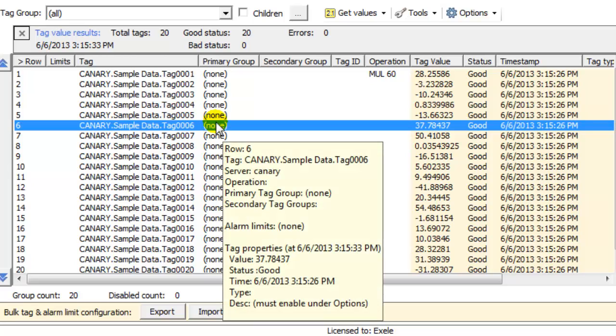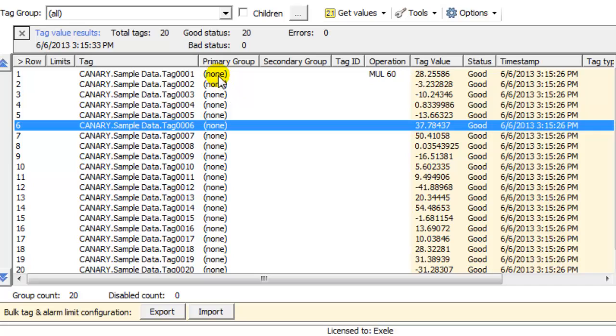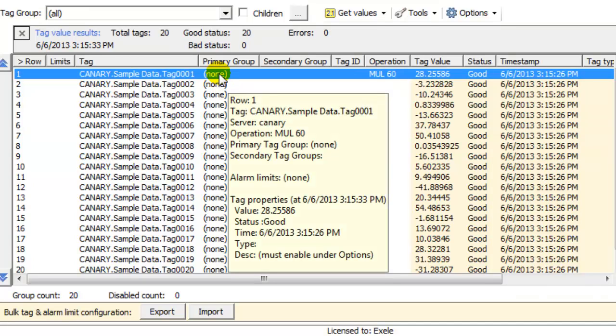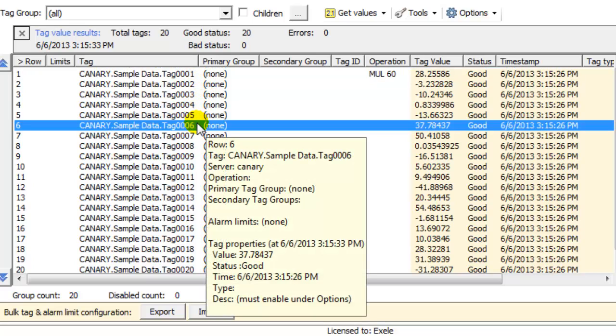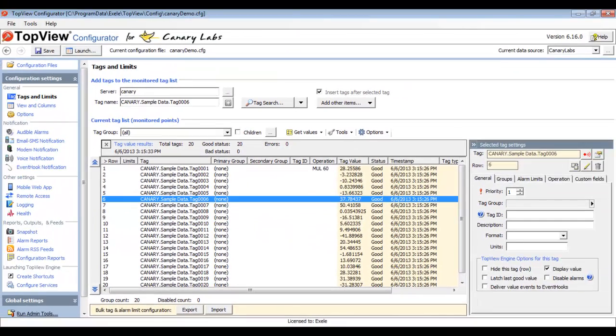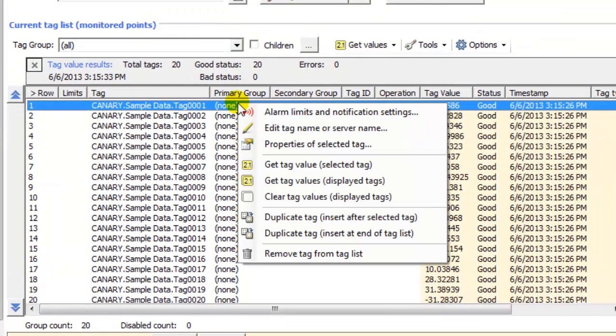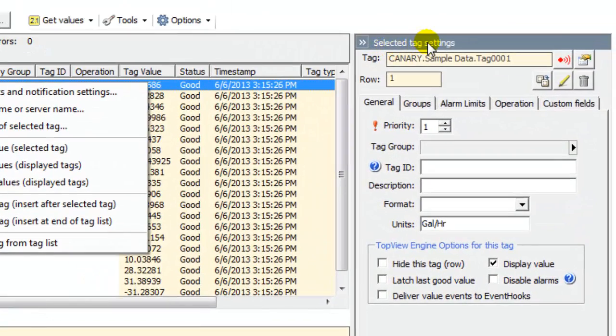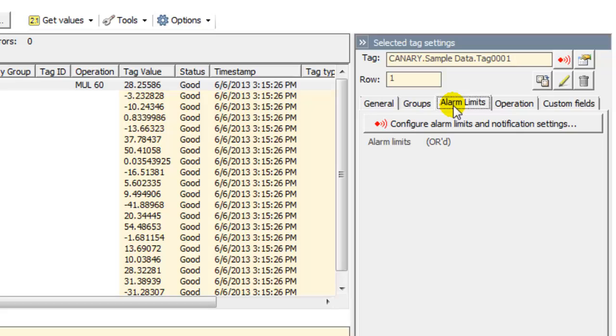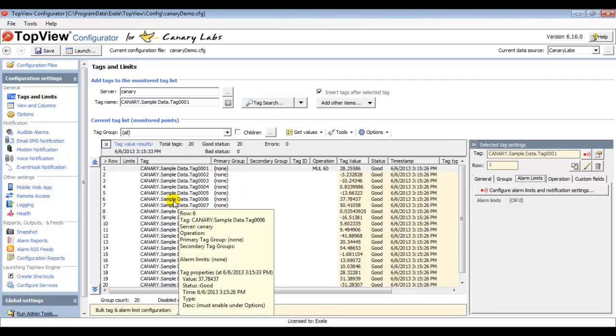The sixth tag is the deviation value. My first alarm condition will be if the flow tag is greater than 1500. My second alarm condition will be if the deviation is greater than 20. To configure alarm limits, we need to display the Alarm Limits and Notification Settings screen, and there are a few ways to do this. You can right-click a tag and choose Alarm Limits and Notification Settings, click the button to the right of the tag name under Selected Tag Settings, click Configure Alarm Limits and Notification Settings under the Alarm Limits tab, or simply double-click any tag in the list.